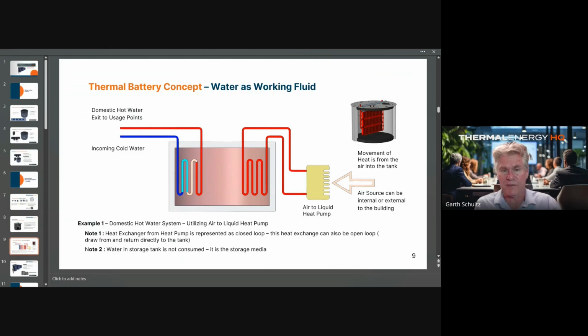And that's of particular importance for us when you're out in market with RO waters that are very aggressive in environments, looking at any metal, even stainless steel, that they can get attracted to and start to pit. With the nylon heat exchanger assembly, someone thinks, well, nylon won't work, but if you lay this design out, it's got large surface area, and for our applications for domestic hot water systems, where there's an RO or potential for corrosion, we address that. But we're kind of heat exchanger agnostic. If you've got a good coil loop assembly, copper, stainless steel, that fits your application, we have designs on that, or we'll assist you in the design of the heat exchanger that meets your needs.